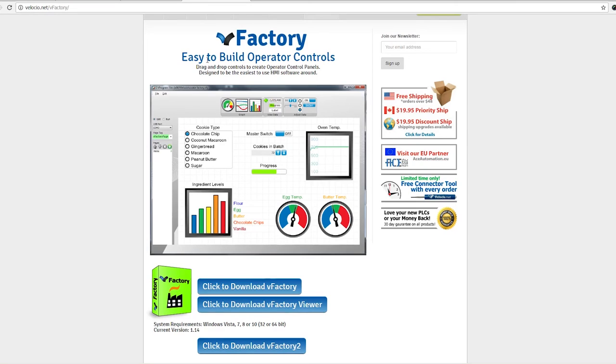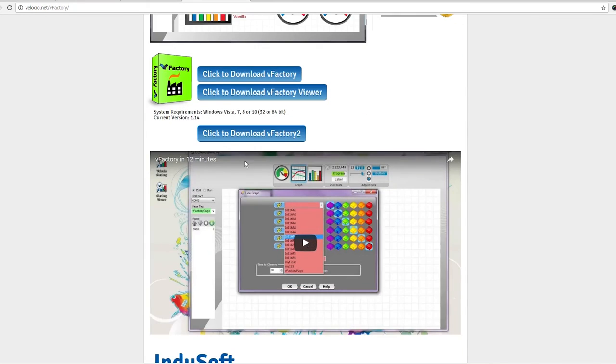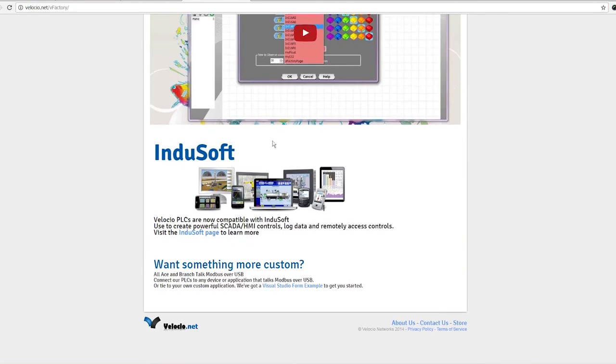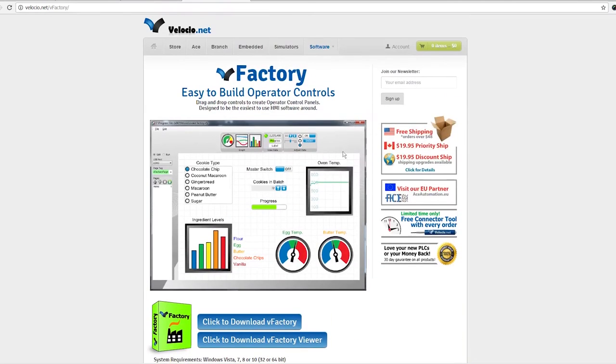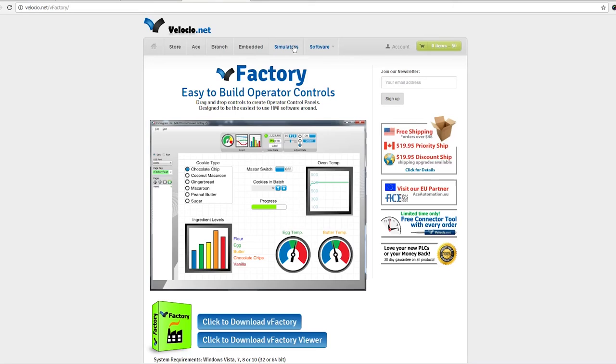Especially with laptops with modern two-pin power supplies, they don't have ground. Sometimes they float away from DC or on true earth ground and you get glitches to interrupt communication and it resets the panel. So your mileage may vary. But with this V Factory HMI software you can plug in by USB and get direct control by having buttons and options as well as gauges and dials and charts of what's going on.